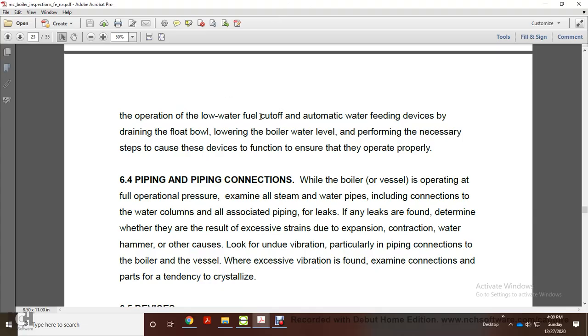6.4, piping and piping connections. When the boiler or vessel is operating at full operational pressure, examine all the steam and water pipes, including the connection to water columns and associated piping, for leaks. If leaks are found, determine whether they result from inspection, excessive strain due to expansion, contraction, water hammer, or another cause. Look for undue vibration, particularly in piping connected to the boiler or vessel.